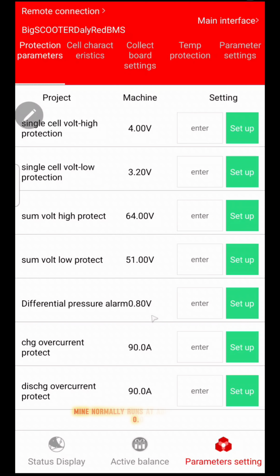Mine normally runs at about 0.3 to 0.2, so I'm well under this, but if you go to 0.8 you'll get an alarm. And you've got charge over current protection and discharge over current protection, so you can set these again to whatever you like as your preference. I've left them as standard as the factory setting.